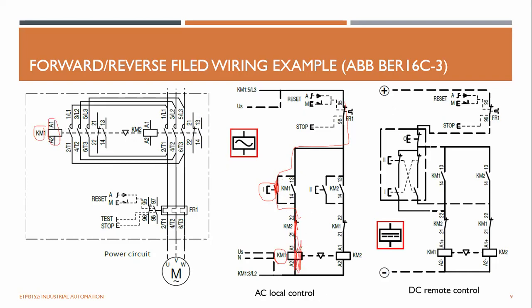And this coil is energized. If this coil is energized, KM1 is energized, which means the KM1 normally open contact will be closed. So this contact will be closed, which means this guy can now release this momentary push button, but the power can still come from here and go from here because it is self-latch, right? So KM1 closes, its contact closes and it is self-latch. So this guy just presses and releases, and it will run in the same direction forever.